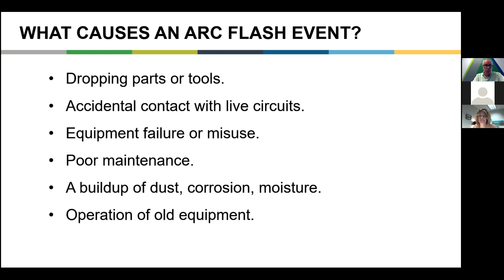So, accidental contact with live circuits, of course, equipment failure or misuse, and poor maintenance. That should ring a bell for most of us because many sites, many facilities don't put a lot of emphasis on maintenance. Buildup of dust, corrosion, moisture should ring a bell too, because it's all over the place in industry, especially the older industries. Operation of old equipment: industrial equipment that distributes power in facilities that have large motors in service is big, powerful equipment meant to switch very high energies. And with that comes very high calories in the arc flash events when they occur.